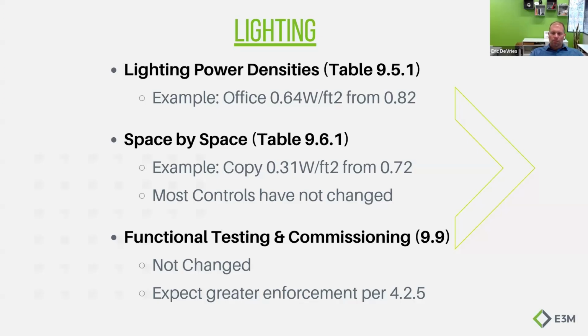The design of lighting has changed. An office used to get 0.82 watts per square foot; you now get 0.64. Space by space, a lot of these things have changed, but this is not hard to accomplish. None of these values are difficult to hit. It's basically saying you're going to design all projects with LED going forward, which most professionals do. You'll really have a hard time hitting some of these dimming requirements, controls requirements, or allowable watts per square foot if you're trying to go fluorescent still. So for any ECs or electrical designers on the call, go LED and you won't have a problem.